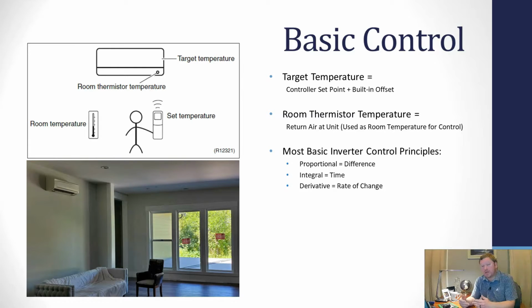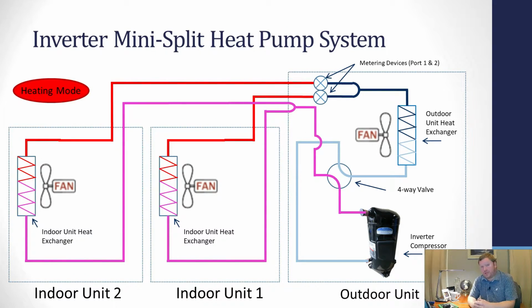When we look at a single zone mini split, everything we just talked about is relatively easy. The compressor is looking at one indoor unit and only running that one calculation to make sure that one indoor unit doesn't overshoot the target temperature. But now we introduce another indoor unit. So indoor unit 1 might be in the living room and indoor unit 2 might be in the master bedroom. This is a very common setup or application. I put a unit in my master, I put a unit in my living room, I call it good. Maybe I have a really small house.